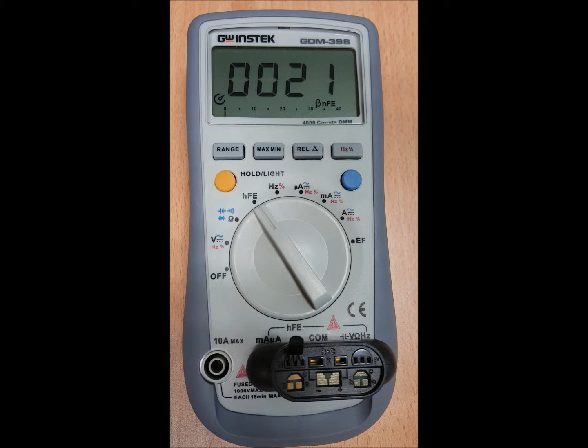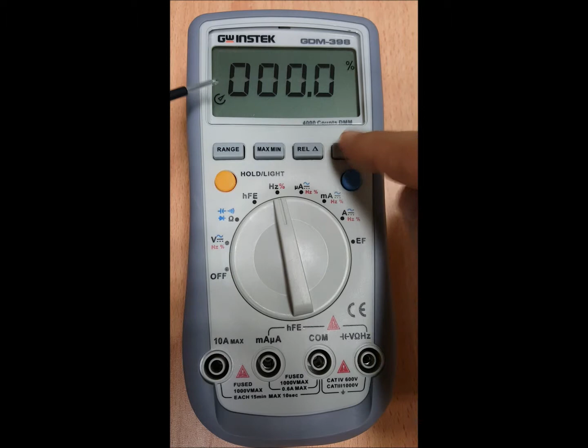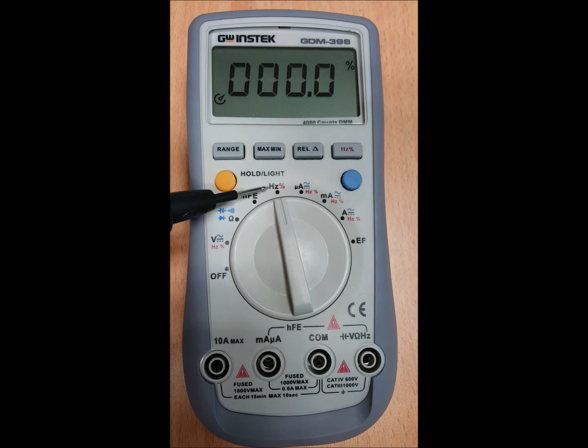Next on the range will be Hertz, which is basically for frequency selection. You can see in this Hertz that percentage mark in red, which was available also on voltage, and you can see it in current as well. You can get to that one always by pressing in here, the Hertz duty cycle. This basically will give you the duty cycle of AC signals. If you are measuring frequency, then you can do either Hertz, which will give you frequency, or pressing in here will give you duty cycle in percentage. Similarly, you can do that on a voltage signal and current signal, assuming all of them are, of course, AC.